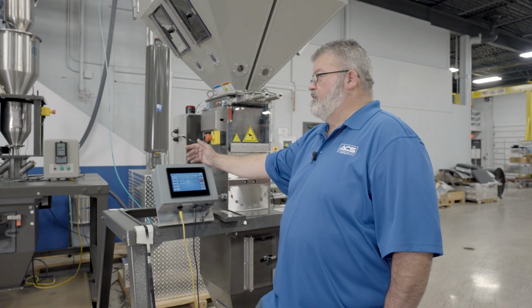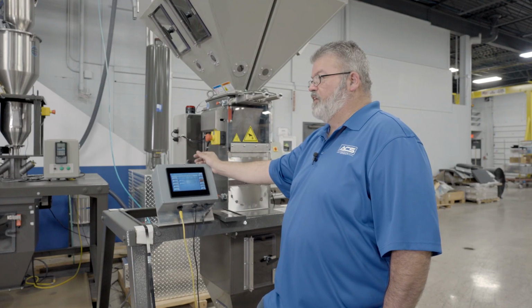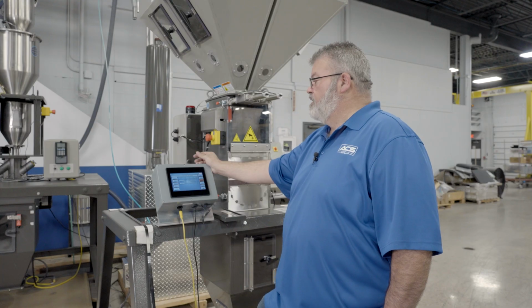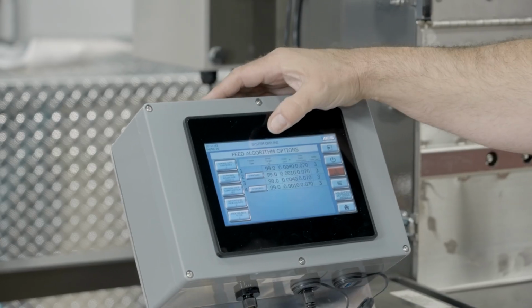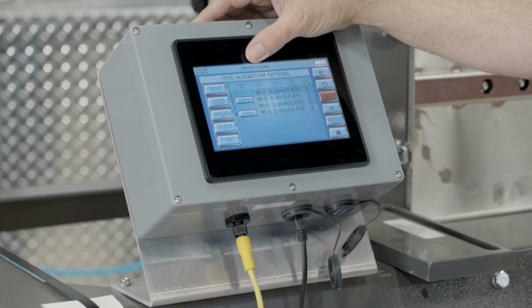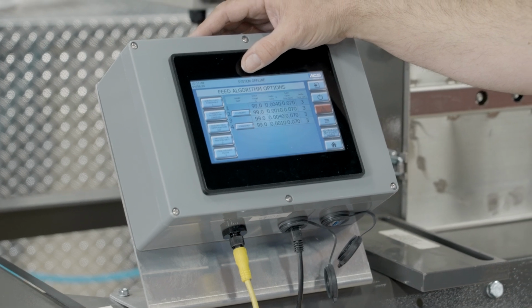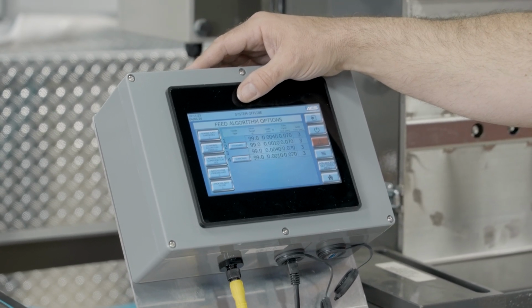So if we need force, like as our example, we had 0.25 pounds per second out of the feeder. If we open that feeder for 4 seconds, we know that we're always going to overshoot the value. So what we do is we open for an initial target percent.